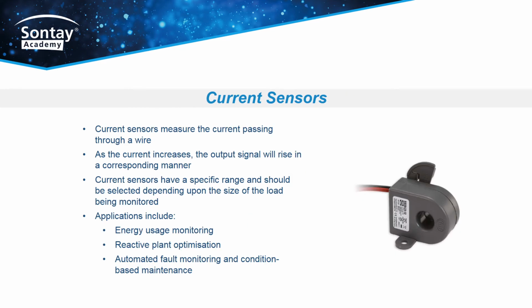Current sensors. Current sensors measure the current passing through a wire. As the current increases, the output signal will rise in a corresponding manner. Current sensors have a specific range and should be selected depending on the size of the load being monitored. Applications include energy usage monitoring, reactive plant optimization, and automated fault monitoring and condition-based maintenance.